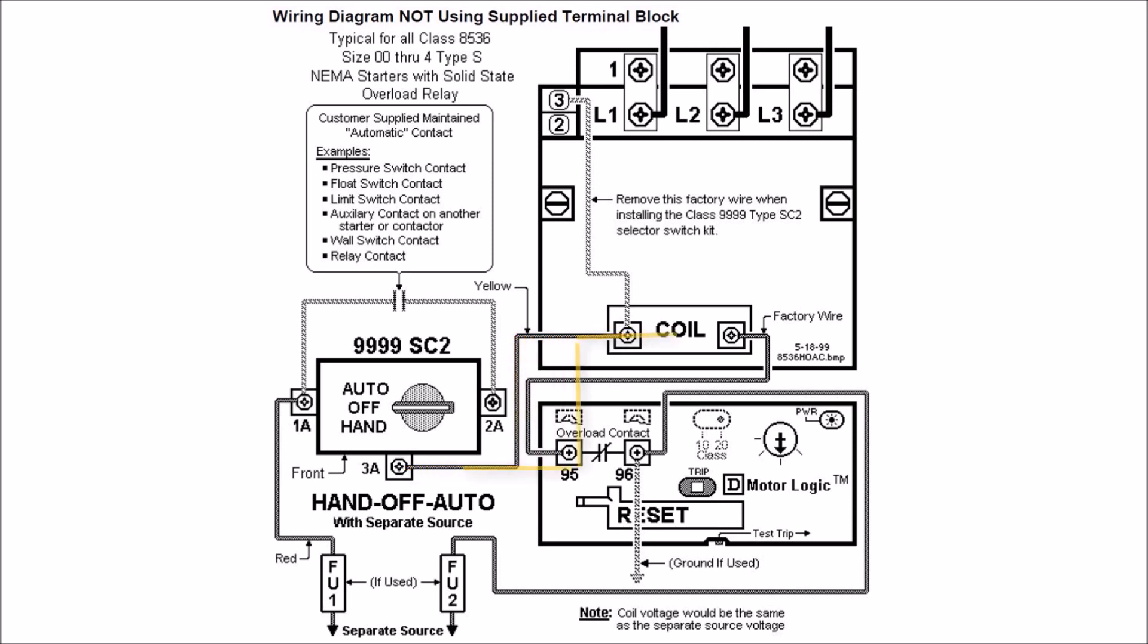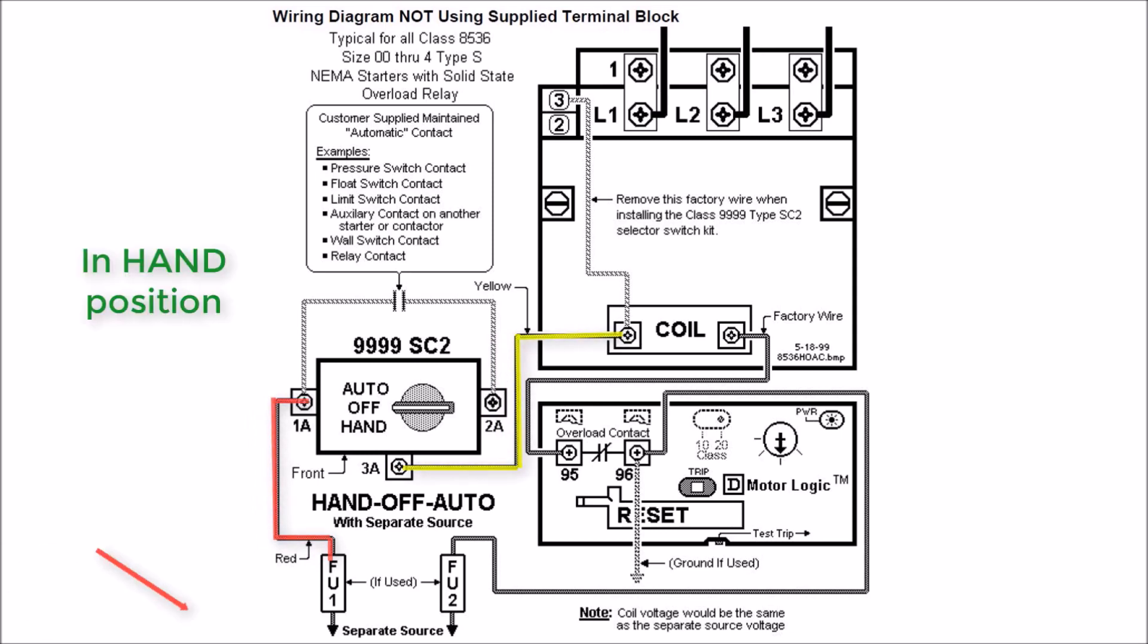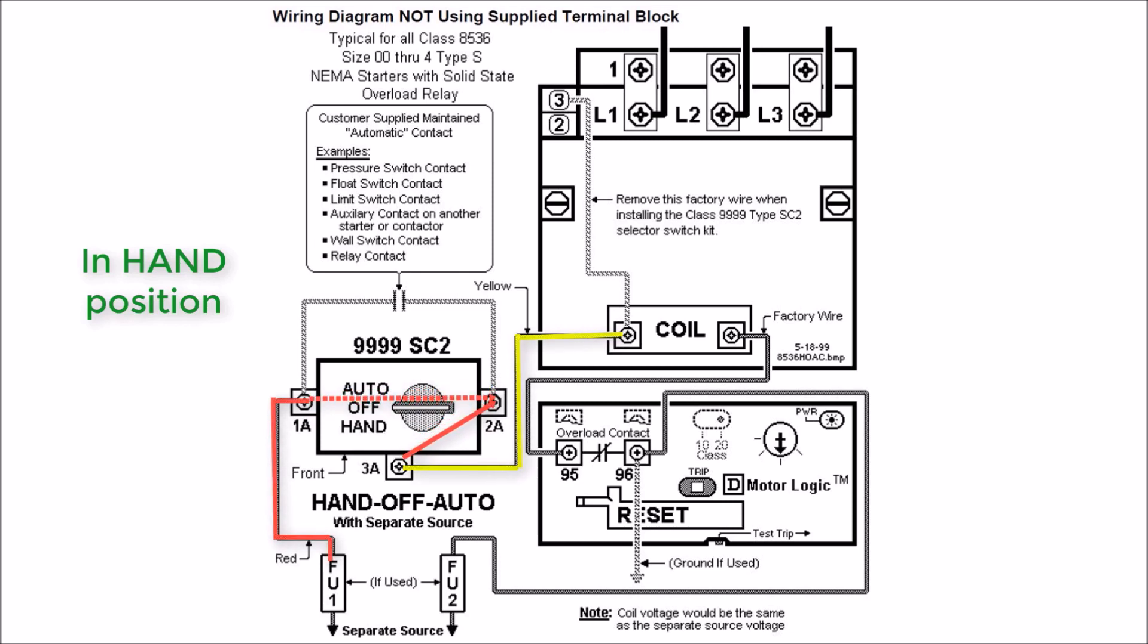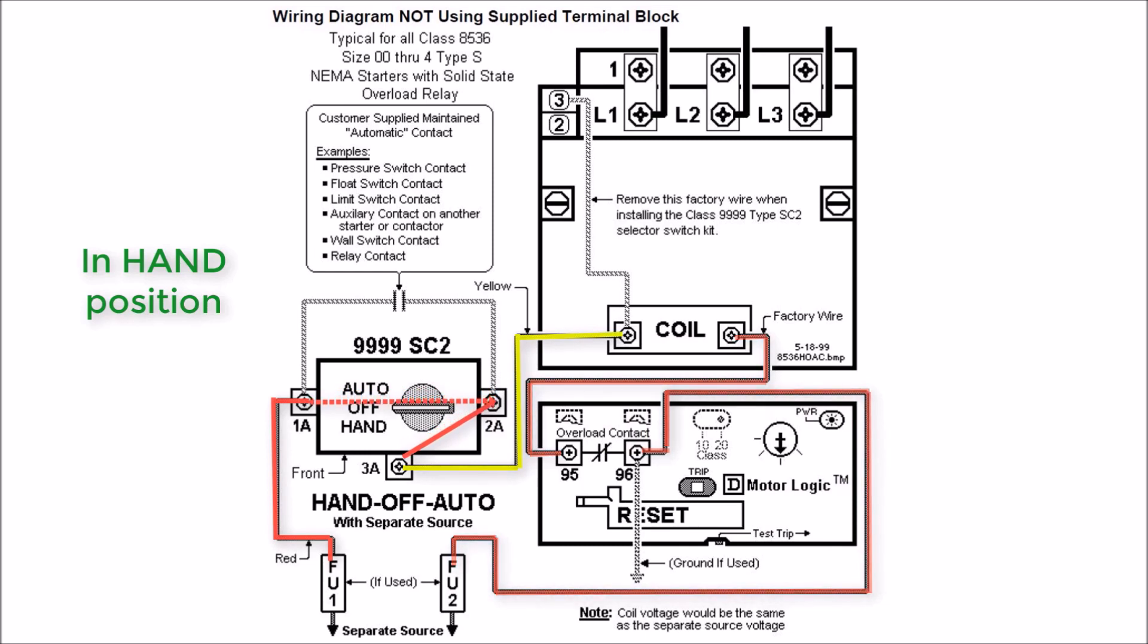The way this handoff auto selector switch works is in the off position, there's no closed contact, so everything's open. In the hand position, you'll have 2A to 3A which is closed, as well as 1A to 2A which is going to be closed as well, taking that line voltage that you have connected to 1A straight to the left-hand side of your coil, engaging your contactor.